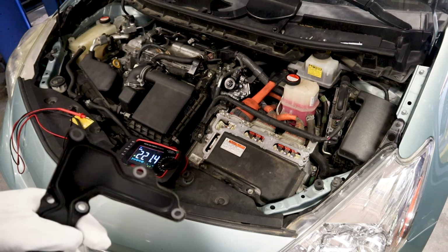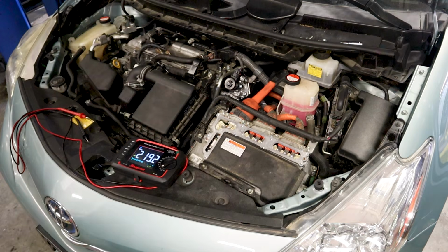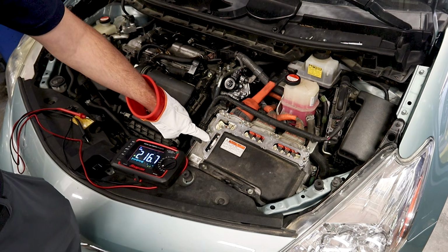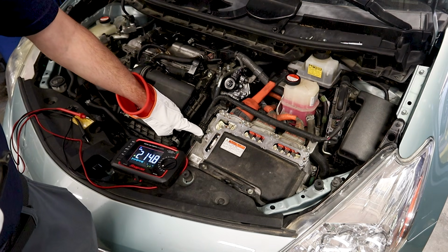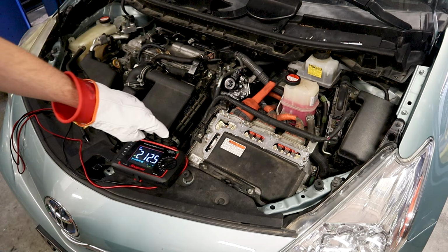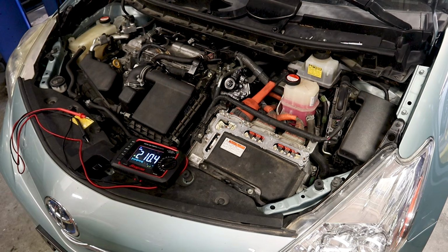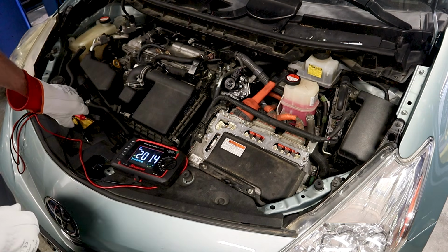So if that happens, there's really nothing we can do to shut it off, which is why we're testing for voltage at this point. Right here is the fuse we'll be removing and doing a resistance check on to see if it's faulty. This goes to the compressor. It's a sand-filled fuse, about 50 bucks if it needs to be replaced, and you can get it from Parts Geek.